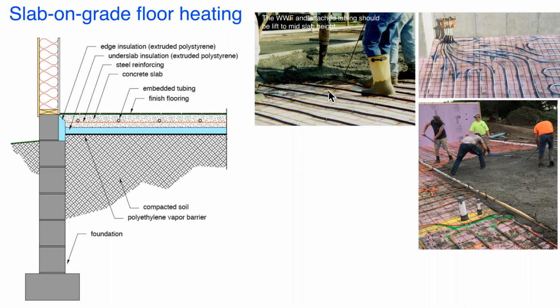And I can tell you, even at 15 BTUs per hour per square foot, that's about a 7-degree increase in water temperature if you leave the tube at the bottom of the slab versus the middle of the slab. That's going to penalize, to some extent, performance of any heat pump, whether it's air to water or geothermal water to water.